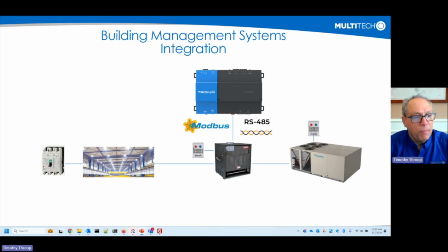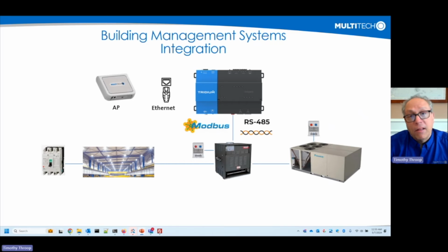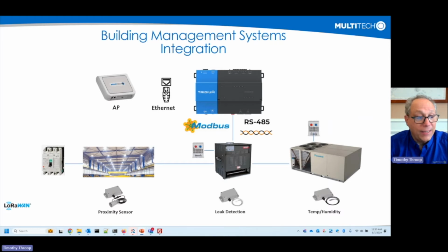Right now, so many building management systems and sensors are controlled via RS-485 and Modbus protocols. They connect into something like a Tridium JACE controller. But when we add our conduit gateway, or our APs, or our IP67 gateways via local area network to the JACE system, we can now add additional sensors into the environment. So you might have existing sensors here that are wired.